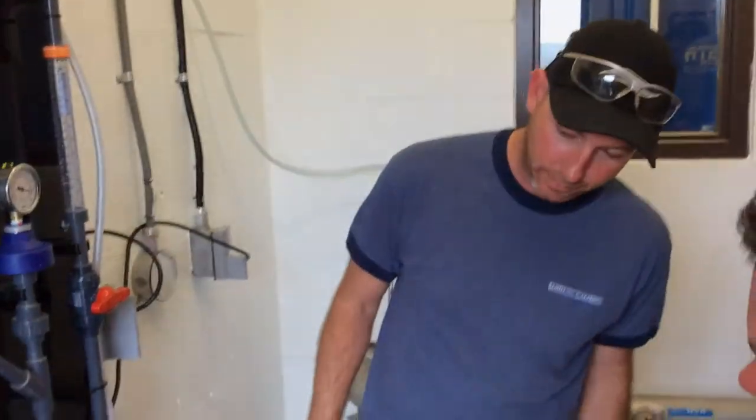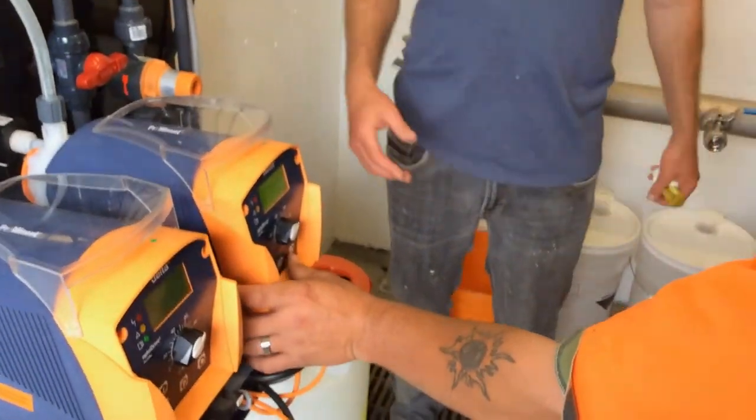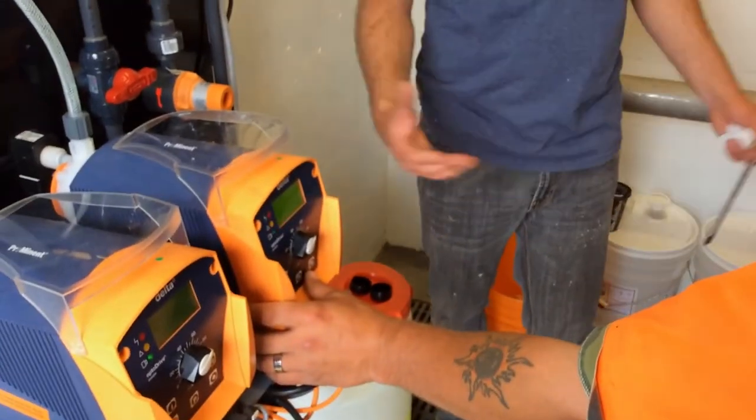So press P once. You can actually slow down your suction. It's meant for high viscosity. So like if I was really sucking something really thick, I can slow down that suction. It derates the pump, and I don't need it. So that's why it's normal. So normal, it's just a regular suction stroke.